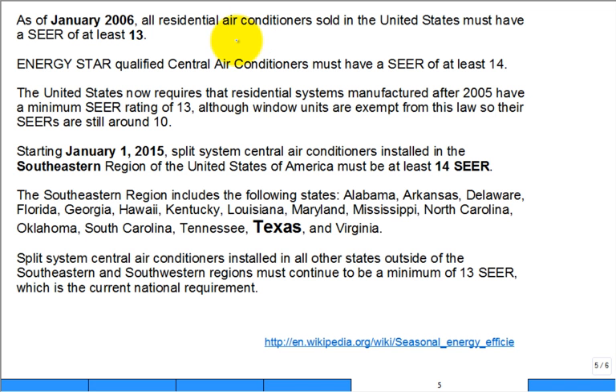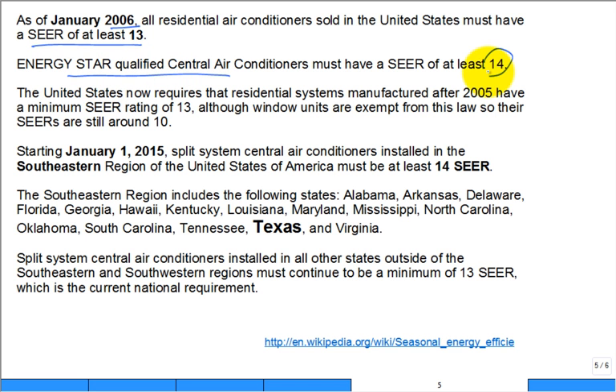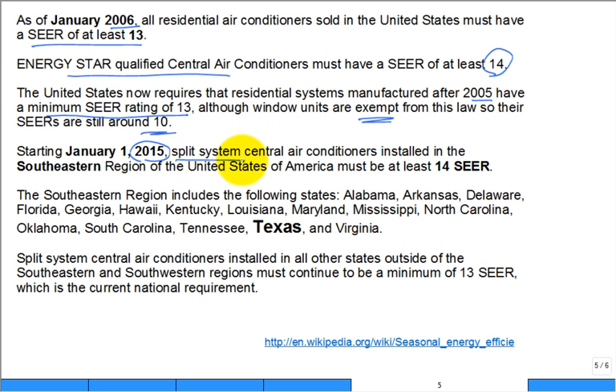There has been a federal push mandating minimum efficiencies in appliances, especially air conditioning systems. Back in 2006, the minimum SEER was set to 13 — manufacturers couldn't sell units below that. To be Energy Star qualified, the minimum used to be 14. Window units were exempt and stayed around EER 10.